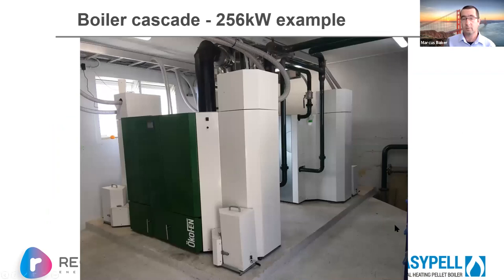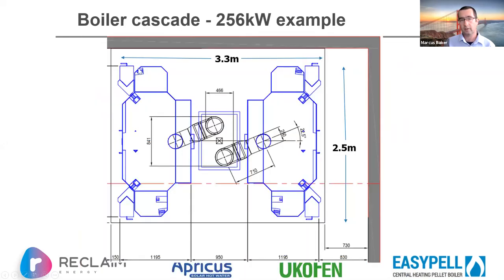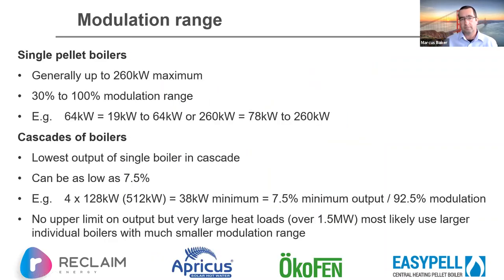As an example, a 256-kilowatt cascade at a college uses two 128-kilowatt units, each with their own pellet feed and pump, with one control system — one master and one slave with entirely balanced duty cycling. The footprint is 3.3 metres by 2.5 metres. They're not as compact as gas boilers but not ridiculous — they'd also fit in a 20-foot shipping container.